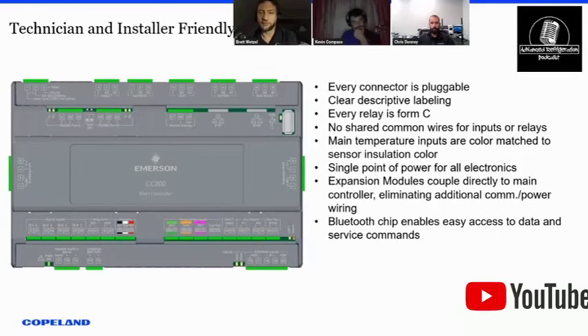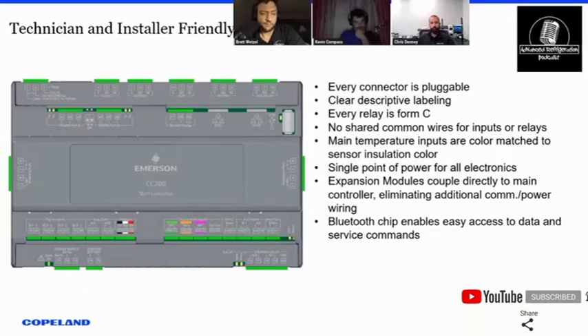So I'm going to ask you this, but I'm not sure if you're going to cover it later. As far as the different grounds you mentioned, there are some case controllers out there that if you do something different with the transformer, it ends up causing a whole bunch of communication issues. Some transformers, they want to be grounded, some they don't. What's your stance on this as far as Copeland?